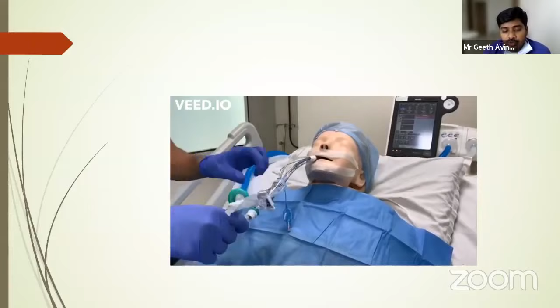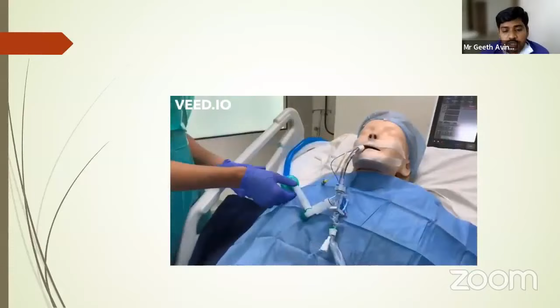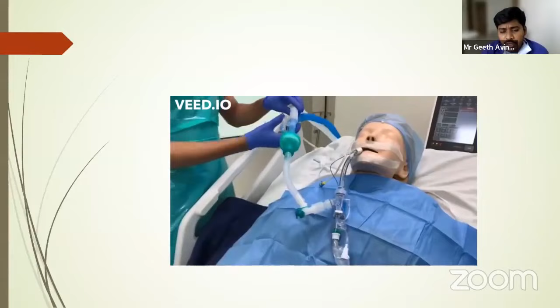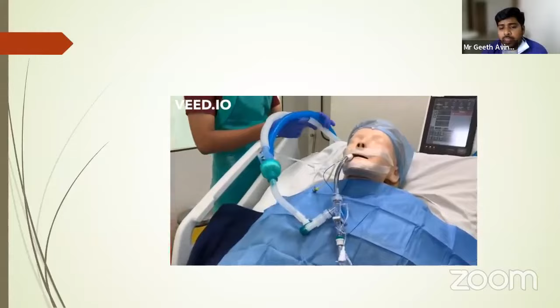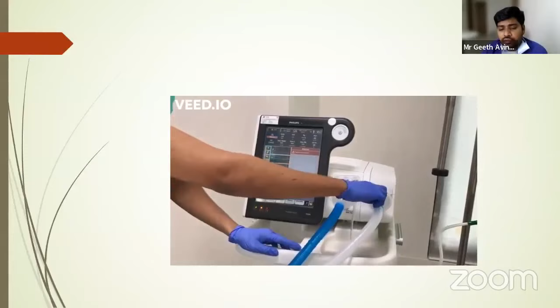Next goes the Y junction, which directly connects one end to the closed suction port. This is a closed suction catheter and this is a catheter mount. Next goes the HME filter. Next go two ventilator tubings which are directly connected, one for inhalation and one for exhalation. And directly we connect two bacterial filters, one to the expiratory valve and the other to the inspiratory valve.